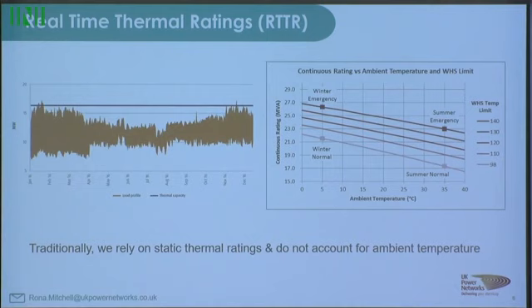This is the real-time thermal rating model. On the left-hand side is a typical annual load profile of a transformer, from January to December. It's not constant - it's peaky in winter times - and the line shown is the thermal capacity of the transformer.